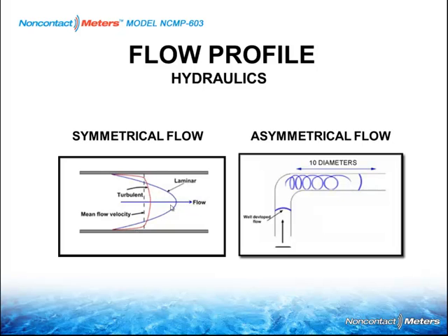This might look like a down view of a guy in a motorboat going down a river with the wake cast out on the side there. These different shapes are defined as Reynolds numbers, and they will change their elliptical shape based upon the flow rate. What is important for this particular technology is that if you were to draw a center line down this pipe, the top half of flow equals the bottom half of flow. And that being the case, with 15 pipe diameters between two 90-degree elbows, you'll have a symmetrical flow profile.